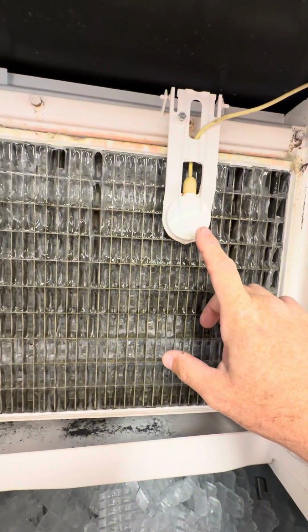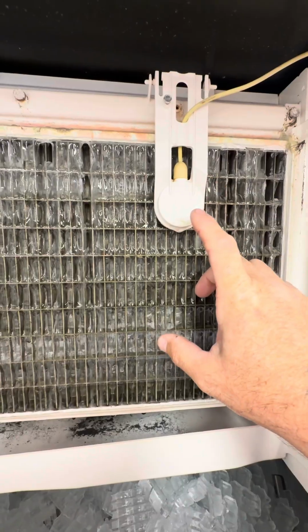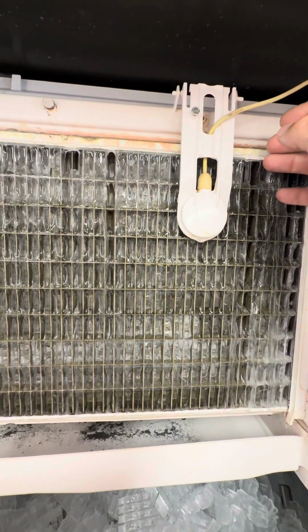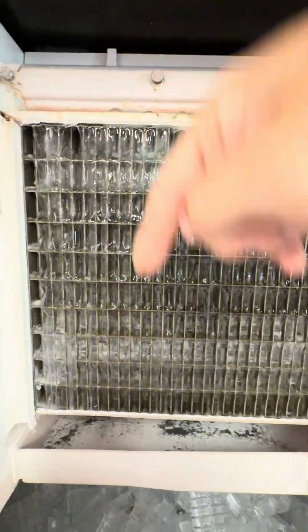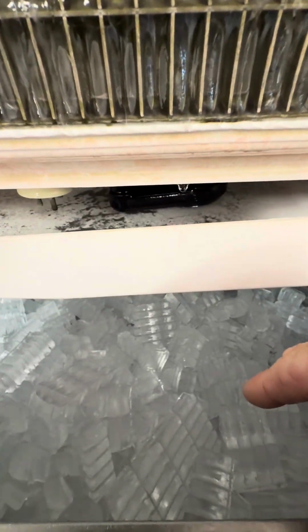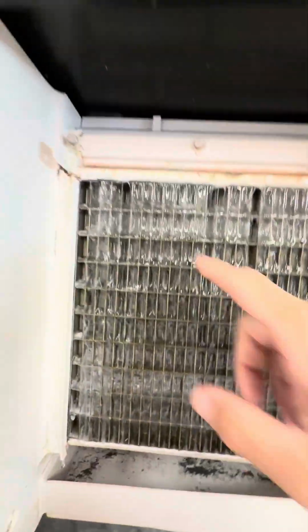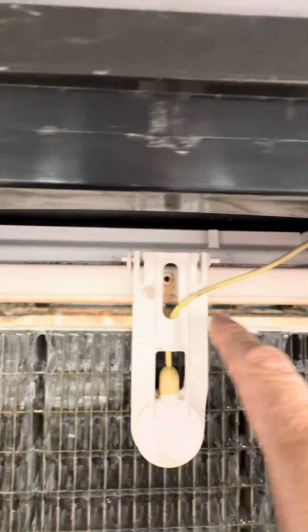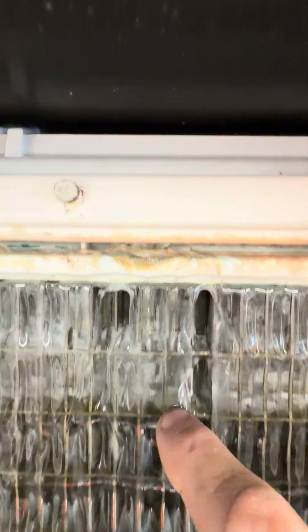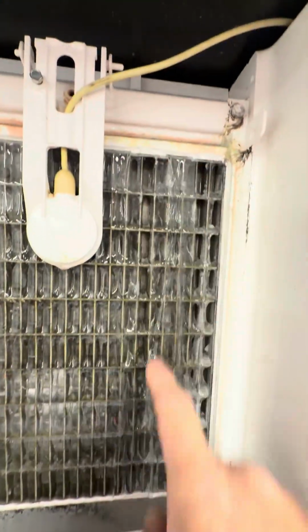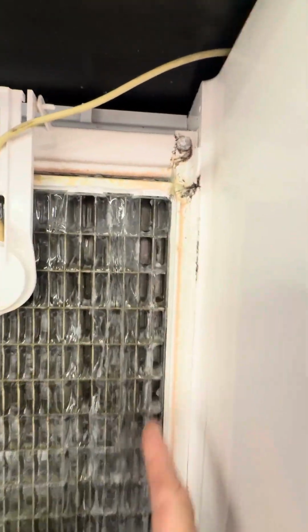When this sensor identifies the ice is hard already, the machine goes into harvest mode, and the ice falls into the bin like this. But look how dirty it is, and in this portion the water isn't running correctly, so the ice isn't forming as a solid block. There are some portions here that don't even have ice built up.